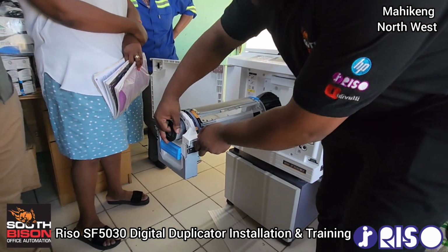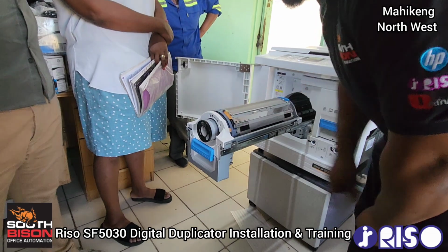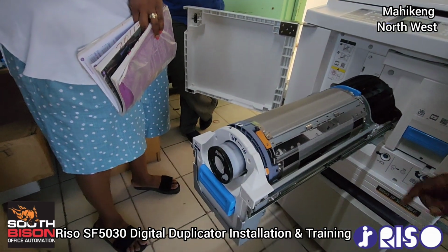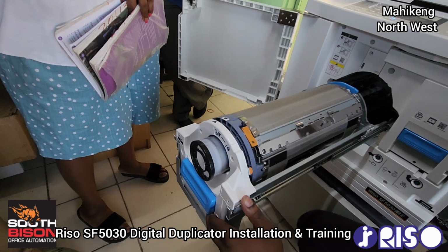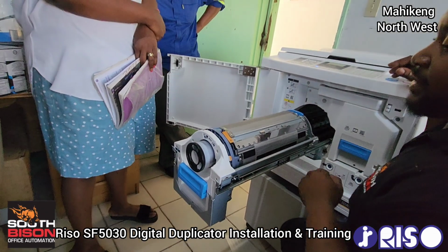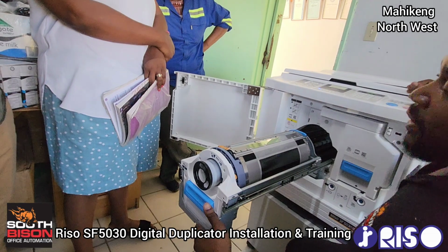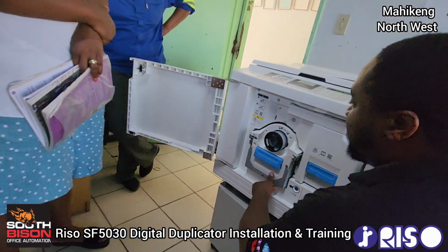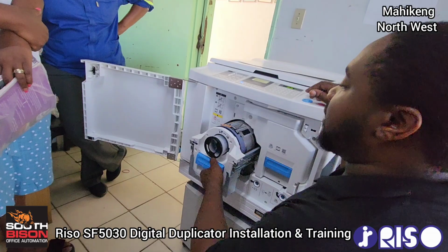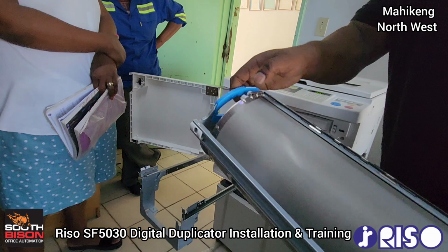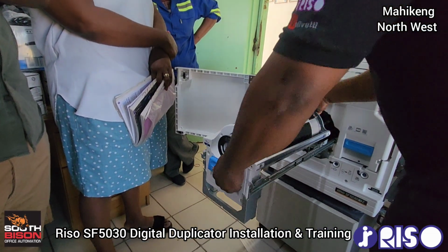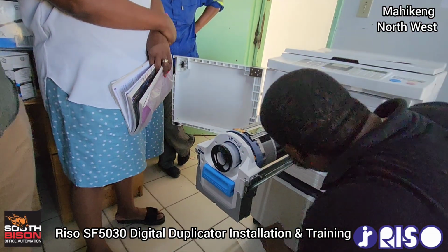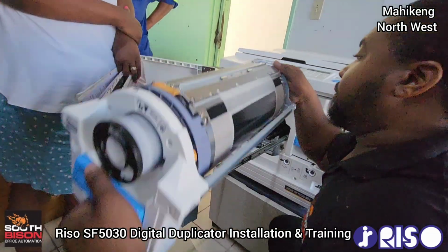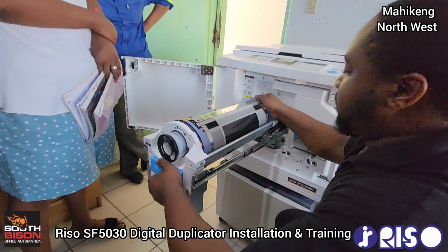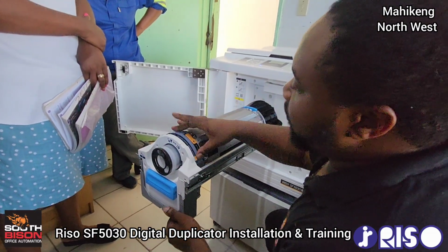When it comes to the drum section, there's an arrow that sits here and another that sits here. This machine is mechanical and has a home position; every time it starts, it has to return to that home position. If this thing is off and I try to close it, it'll make a sound and won't lock in place, because at the back of the drum there's a gear. If the gear isn't sitting properly, you won't be able to communicate with the machine. At the back there's a slot you must line up. So now I push it back to the home position.